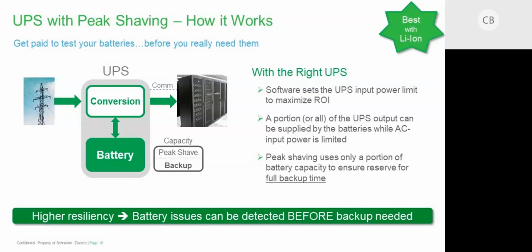So how does it work? Here, on the left, you have the utility grid that's coming into your facility. It's feeding your UPS systems, which are doing some power conditioning before it feeds the load. And you have these batteries tied to these UPSs. But with the right software and the right UPS, you can now utilize any excess capacity in those batteries to do some peak shaving. You can also expand the battery plant on the UPS so that you can get even greater peak shaving capability. Like I said, traditional UPS may be designed for 5, 10, 15 minutes of battery runtime, but there's nothing stopping you from adding another hour's worth of runtime capacity on those UPS systems, and now taking full advantage of it versus installing a separate independent battery energy storage solution.